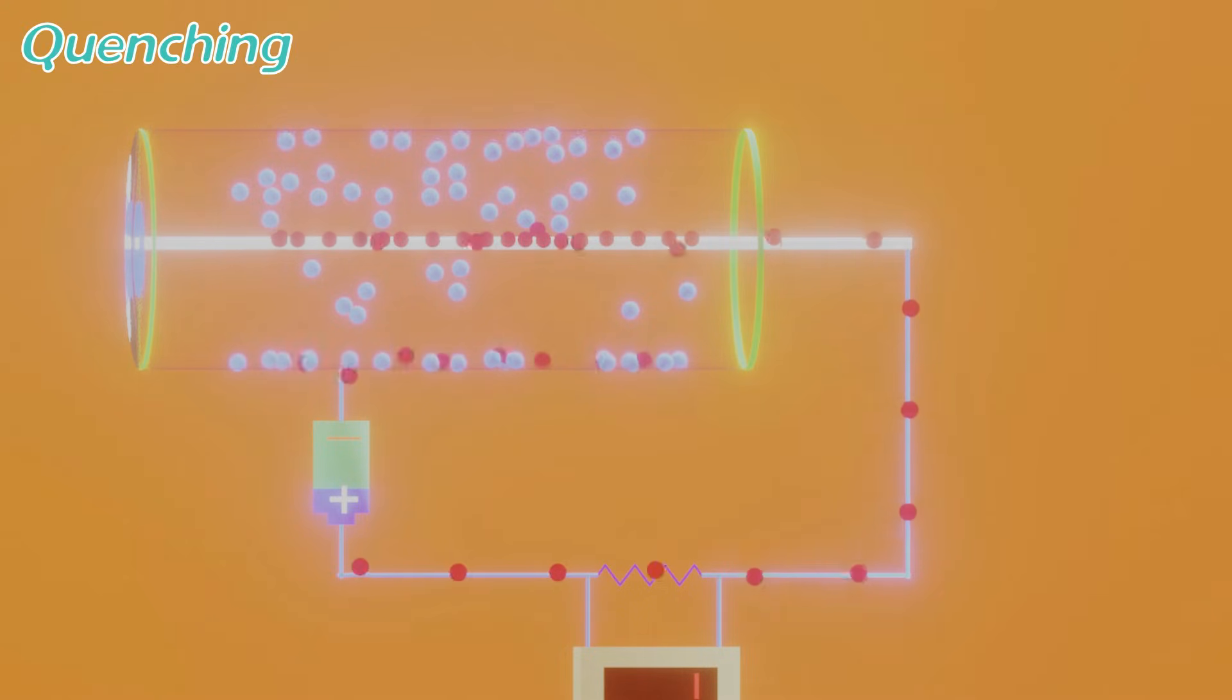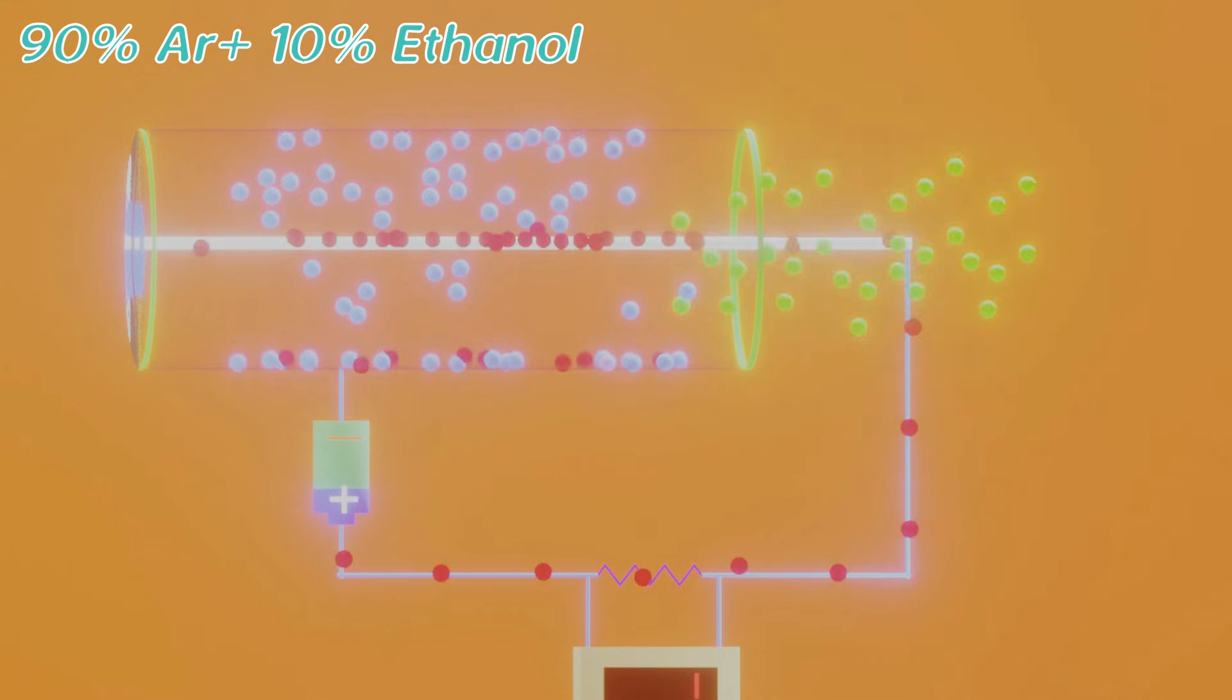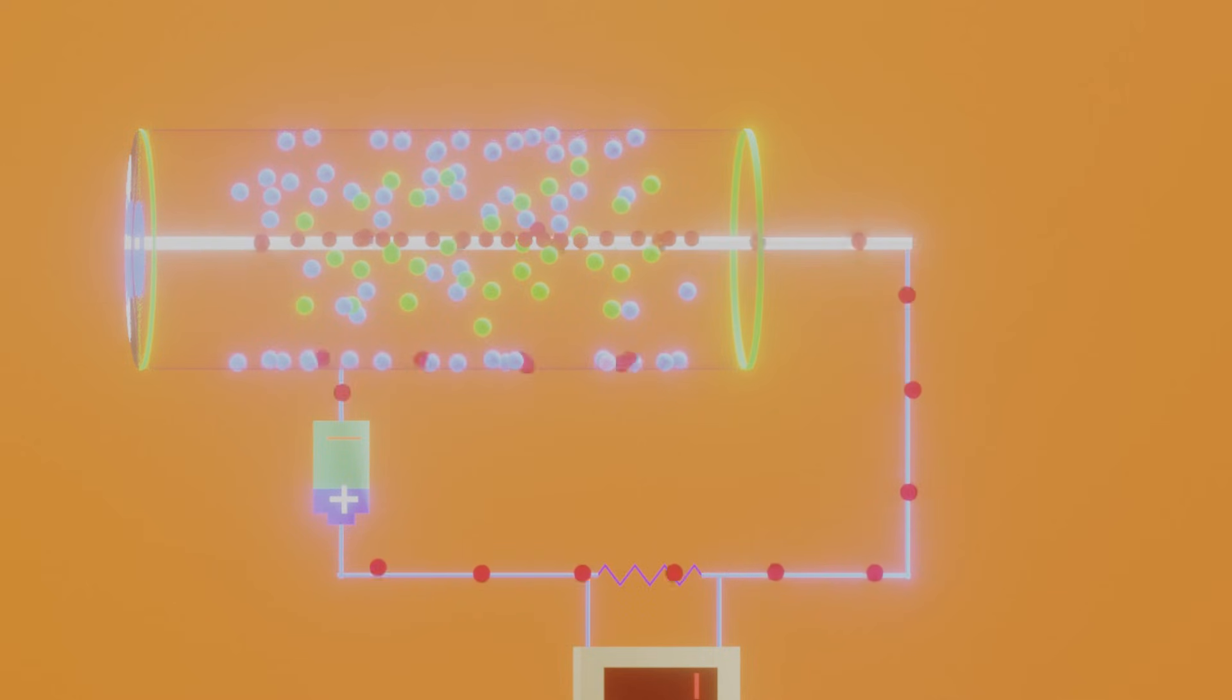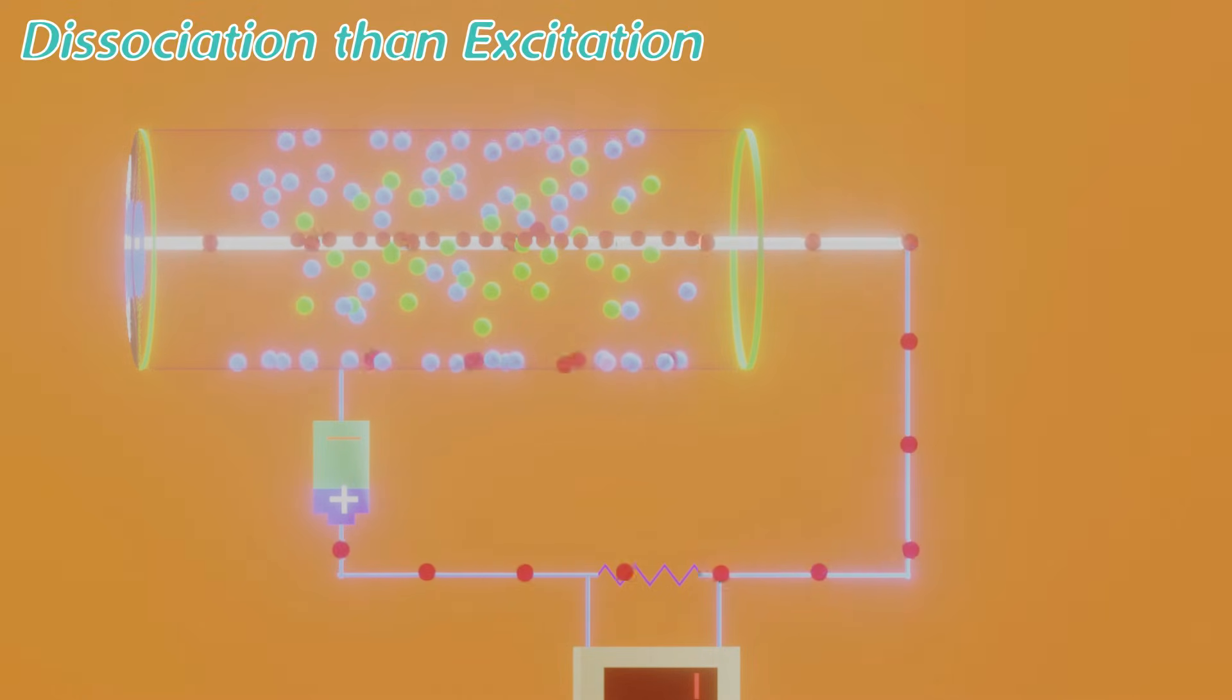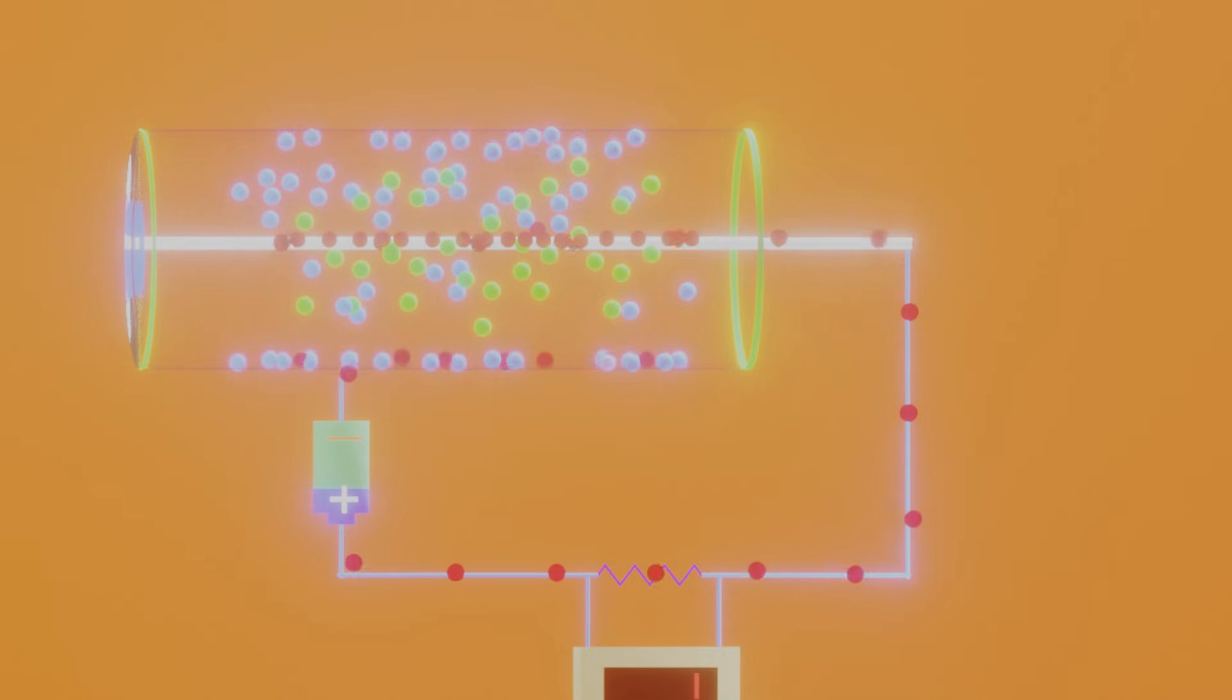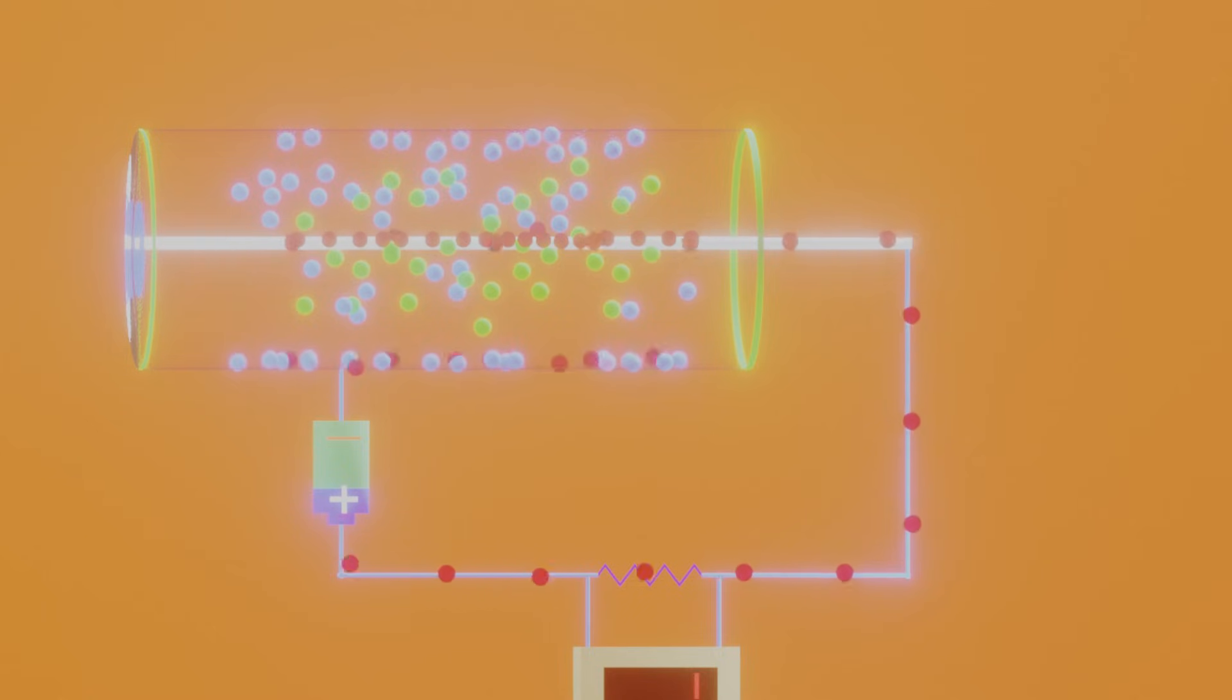For this we use quenching. For this we fill the GM counter with 90% argon and 10% ethyl alcohol. And one interesting feature of alcohol is that its large polyatomic organic molecules favor dissociation then excitation. As a result it doesn't go to the excited state, and no UV or other radiations are emitted in this process. And hence a second avalanche can't start. So we'll get a correct count this time.